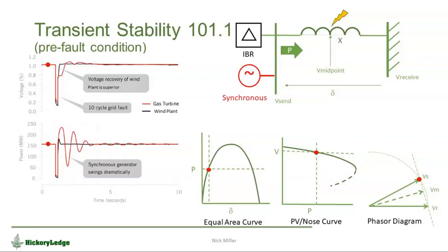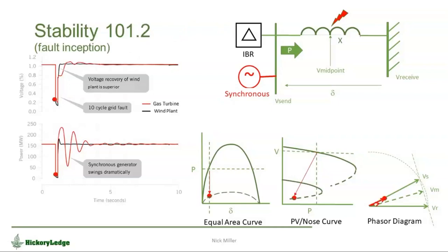So let's look at what happens when we put a fault on. This slide is the instant that the fault is applied. There's been no acceleration of the inertia of the synchronous machine. The voltage has collapsed. It goes down to some point related to the apparent impedance and the fault current delivery of the synchronous machine. The PV curve is collapsed. And in general, during the fault, we are on the underside, the unstable locus of the multi-root equation of the voltage. So the red arrow shows where the red dot has migrated to. Sending end voltage has collapsed, but hasn't moved yet. So we all recognize that.